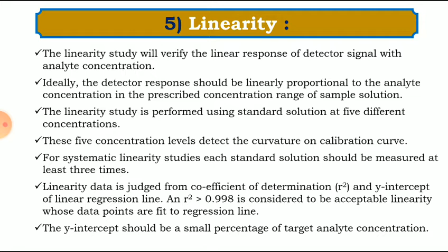Then linearity data is judged from the coefficient of determination, that is R square. Linearity data is the coefficient of determination, denoted by small r square, and the y-intercept of the linear regression line. When we plot the calibration curve with the help of 5 standard solutions, we will get a straight line graph, right? When we extrapolate that straight line, it will intercept the y-axis. The r square greater than 0.998 is considered acceptably linear, whose data points fit the regression line. The y-intercept should be a small percentage of the target analyte concentration.